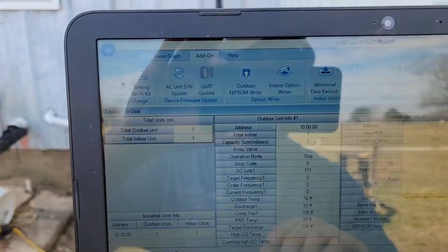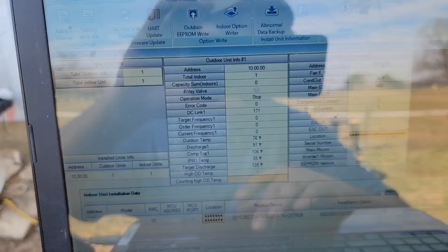Okay, we can look right here, it says SNET Pro 2 CAC inverter. You can see a bunch of information populated here, but to write my option, because I had an error code E470 right there where it says error code, I go to outdoor EEPROM write. Once I get that SRC file, I click the address, then go to open option file, and my SRC file is right there.